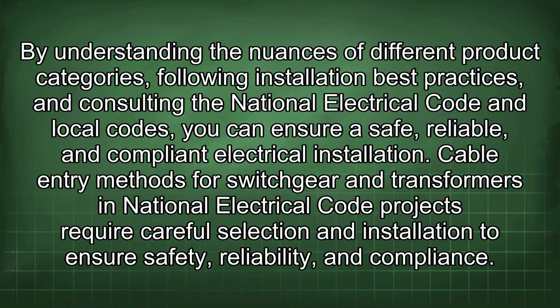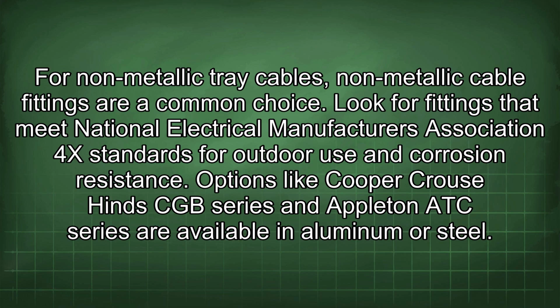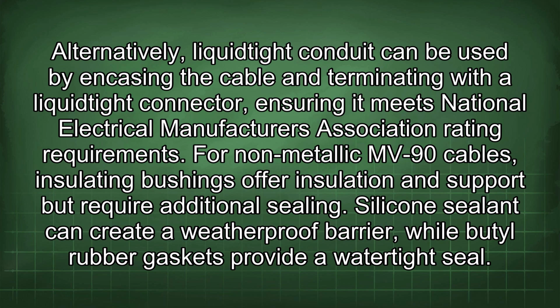Cable entry methods for switchgear and transformers in National Electrical Code projects require careful selection and installation to ensure safety, reliability, and compliance. For non-metallic tray cables, non-metallic cable fittings are a common choice. Look for fittings that meet National Electrical Manufacturers Association 4X standards for outdoor use and corrosion resistance. Options like Cooper-Crouse-Hinds CGB series and Appleton ATC series are available in aluminum or steel. Alternatively, liquidtight conduit can be used by encasing the cable and terminating with a liquidtight connector, ensuring it meets National Electrical Manufacturers Association rating requirements.